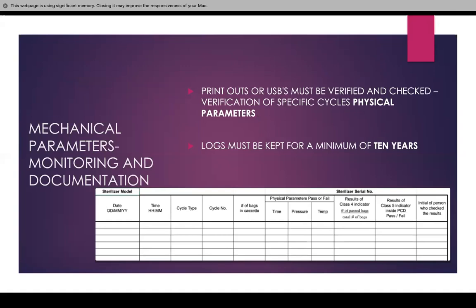Some sterilizers have USB devices, others have printouts, others don't have anything. If you have a USB plugged in within your sterilizer, you have to download the data on a secure computer that you can keep a record of for 10 years showing that it has passed — temperature, pressure, and time. If it is a printout, you must also record and keep those, and it will indicate whether it passed or not.